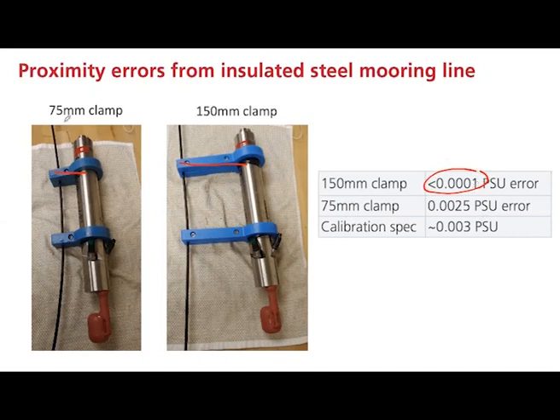Now with the 75 millimeter clamp, of course, the cell is closer to the wire. And in that case, we found an error that's basically at about what you would call the calibration specification, so 0.0025 in salinity. We don't calibrate in salinity, but that would be roughly the calibration error. Or that would be the effect on conductivity, enough to cause an error in salinity of 0.0025. So these are quite minor.